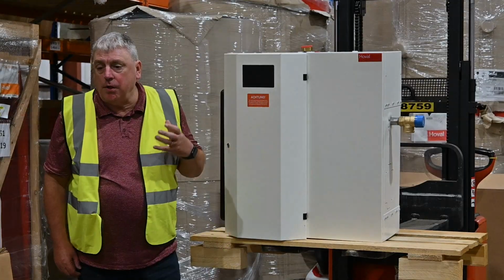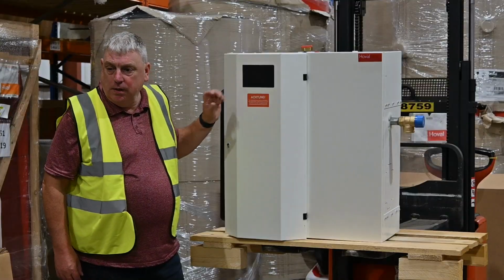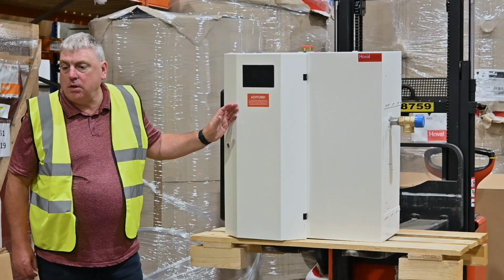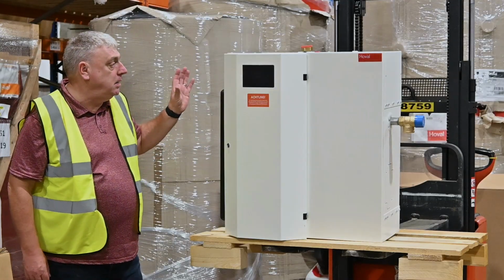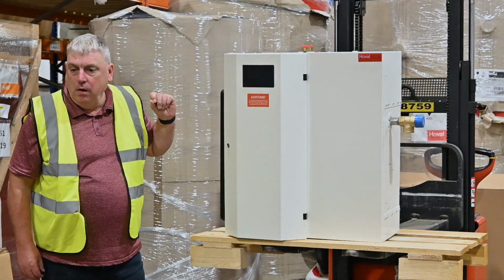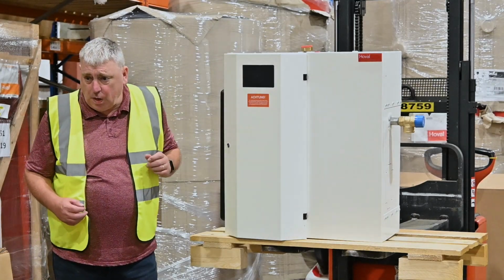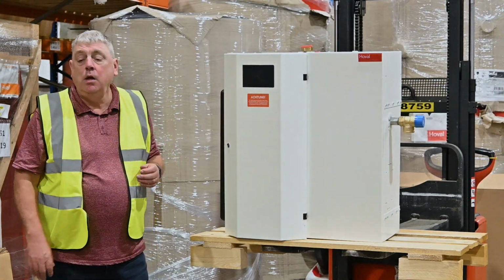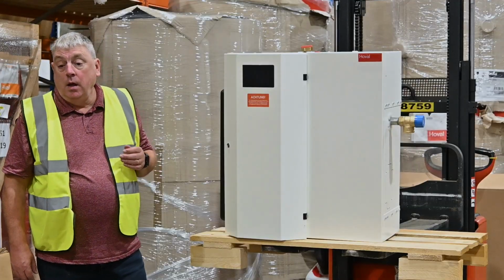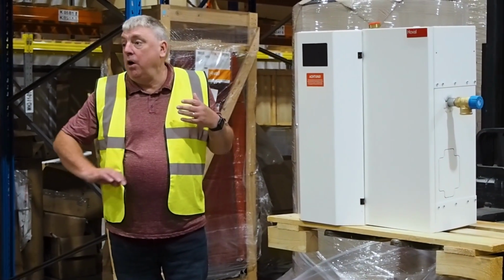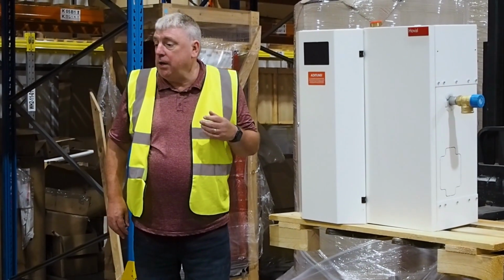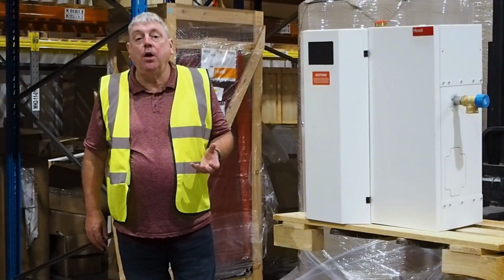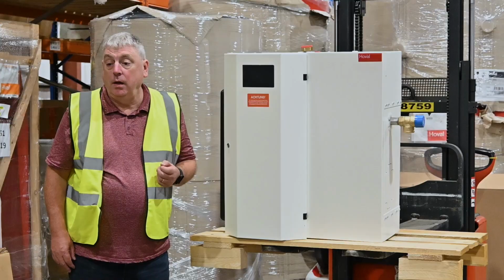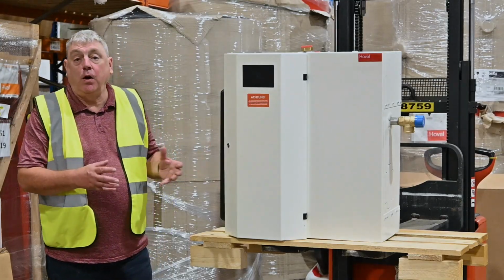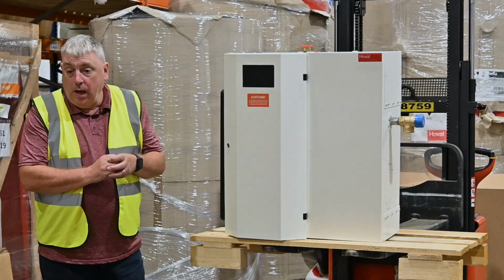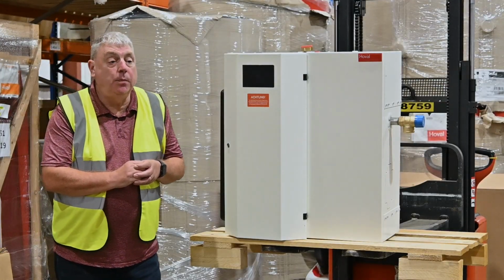So the design intent of these devices, the TransTherm aqua units, is to take a heating supply at 65 or 70 degrees C from our heating device, and then utilise the temperature of the cold water main to drive the heating return back to our heat generators to something closer to 30 or 35 degrees C, while still making sufficient volumes of secondary water at the temperature it needs to be.